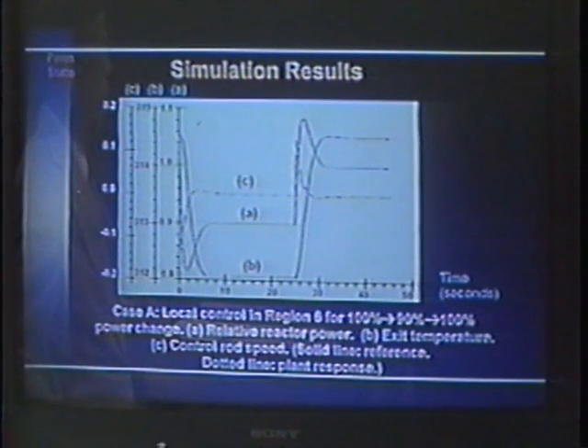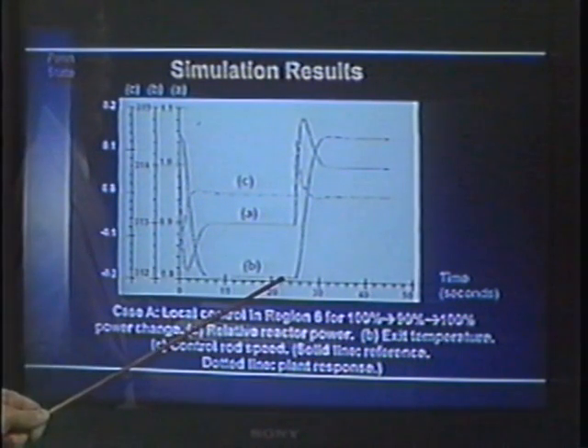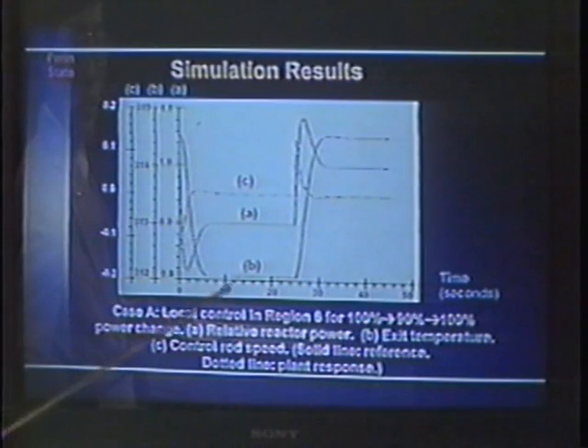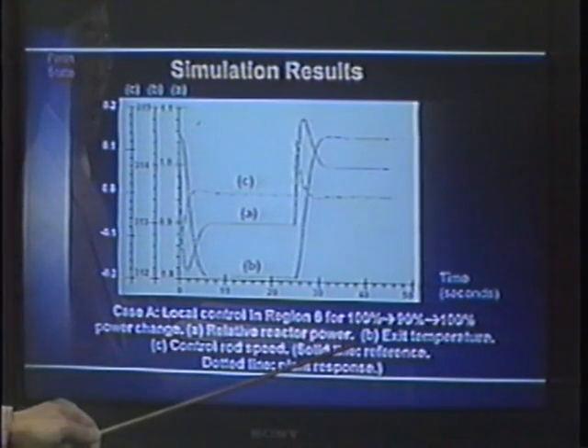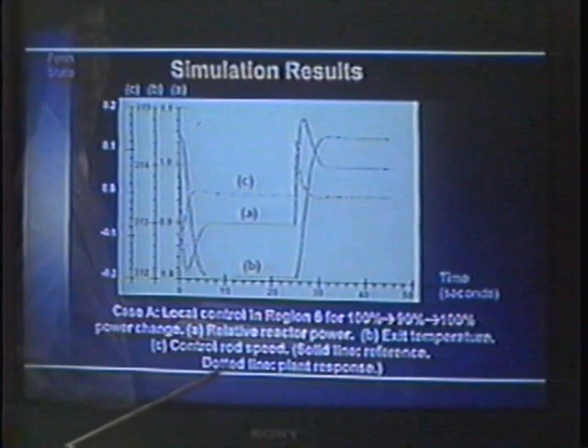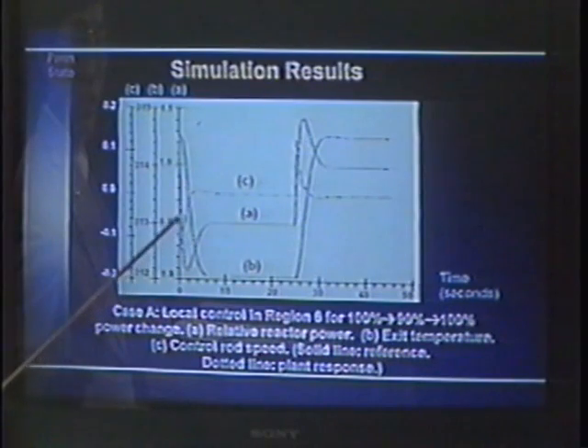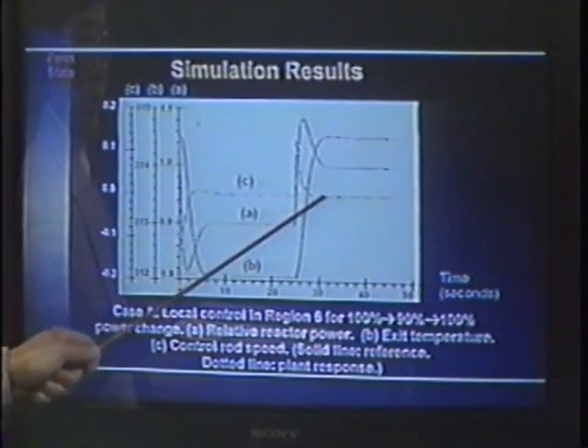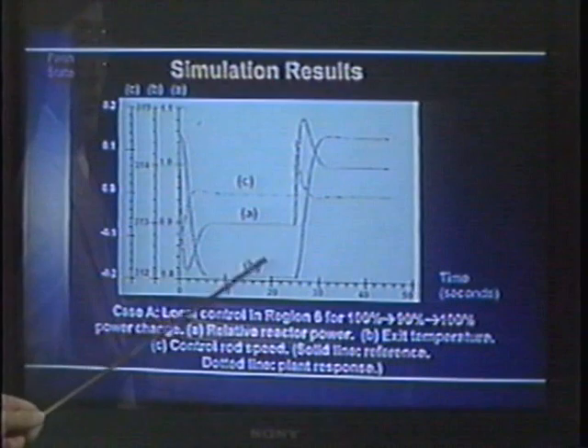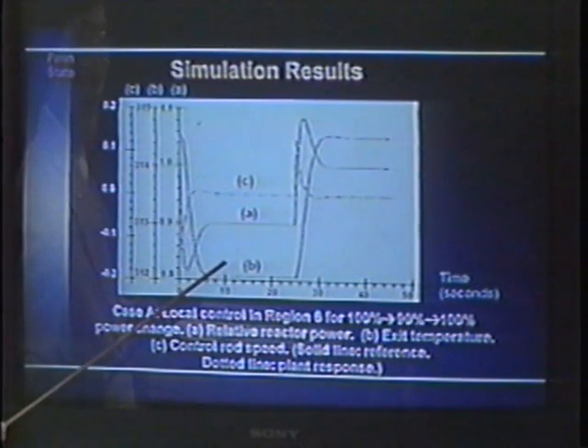However, a more important parameter is B, which is temperature, because temperature gives thermal stress to the mechanical component. So we want the temperature to change very smoothly and yet very rapidly. This is the temperature or exit temperature response. Finally, C is control rod speed. The control rod moves with quite a bit of overshoot in order to produce the response we are having.